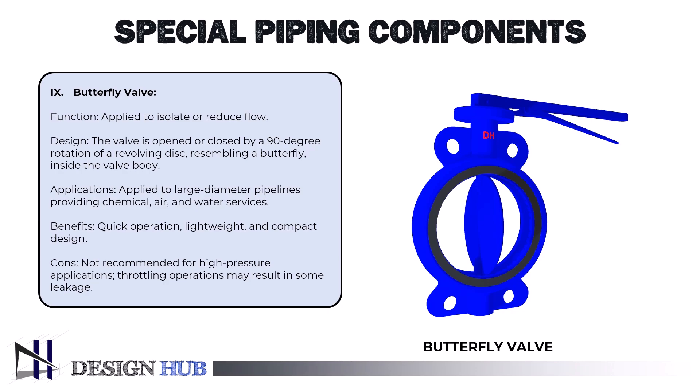A butterfly valve belongs to the quarter turn valve family. When the disc rotates a quarter turn, the valve is fully open or closed. On a rod, a metal disc is positioned as the butterfly. The disc is rotated to fully block the channel when the valve is closed. The disc is turned a quarter turn to permit nearly unfettered fluid circulation when the valve is fully open. The valve can also be opened gradually to reduce flow.